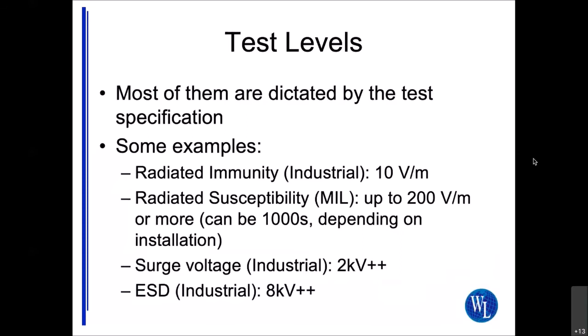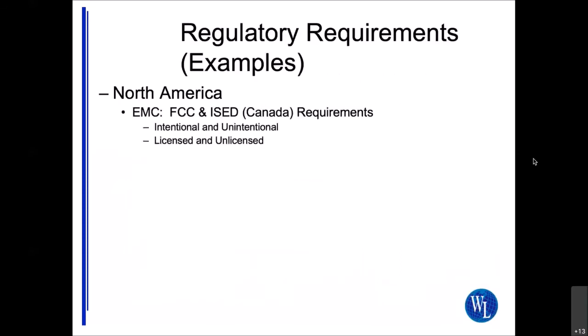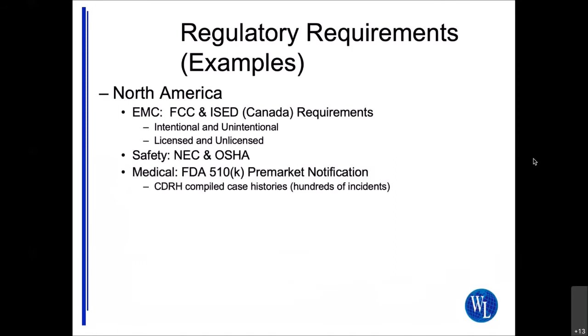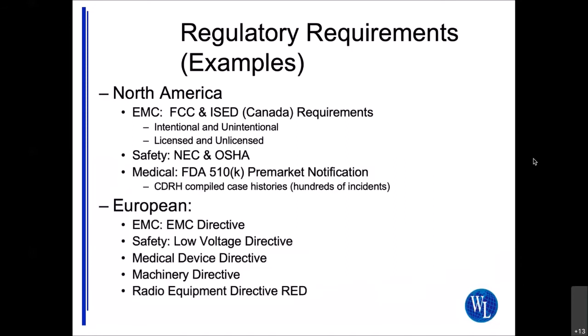In the United States we have the Federal Communications Commission for EMC in North America, and ISED in Canada. They have different classifications for different types of devices. On the safety side, which is related because it's in the compliance arena, we have the National Electrical Code and the Occupational Safety and Health Administration, which pretty much regulate safety. On the medical side we have the 510K, again under the FDA. On the European side we have the EMC Safety and Medical Device Directive, and more prominent in our world, the Radio Equipment Directive, because more and more devices are integrating radios.